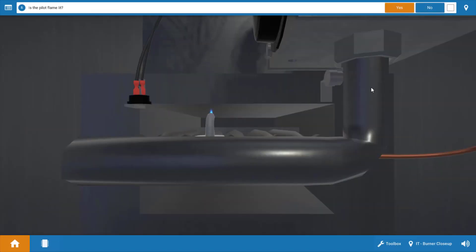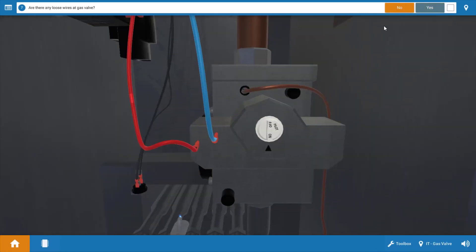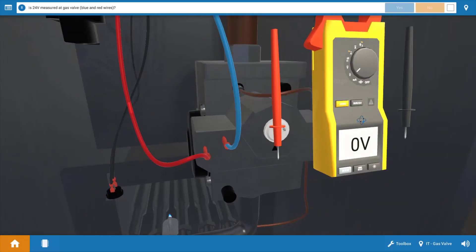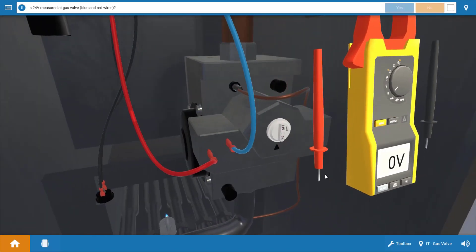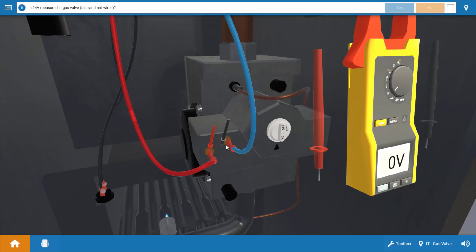We've already established we do have a pilot flame. Next we want to inspect for any loose wires and we'll look at the gas valve first. It appears that all wiring connections are secure so we don't have any loose wires. Next we want to check to see if the gas valve coil is receiving 24 volts. We're going to place the meter leads across the coil connections on the gas valve and when we do this we have zero volts, which indicates that the gas valve is not receiving 24 volts.